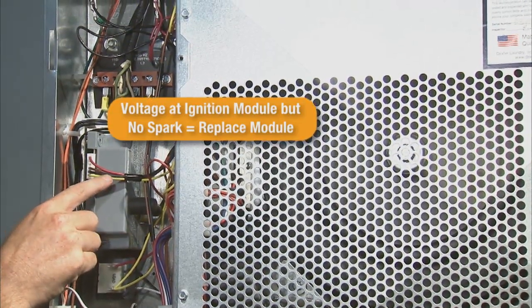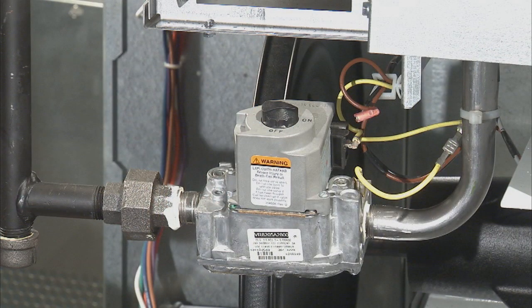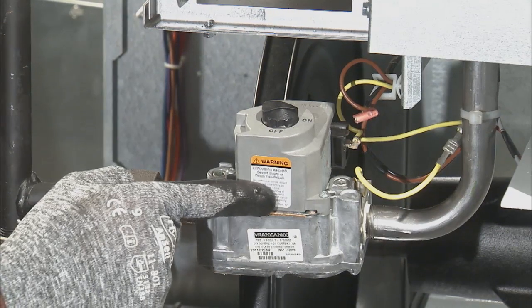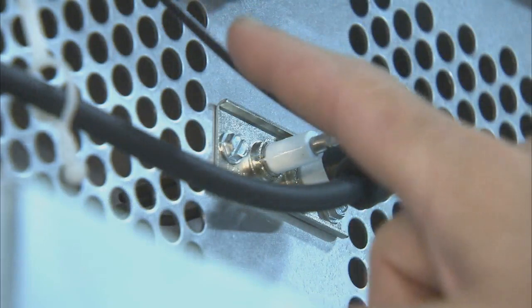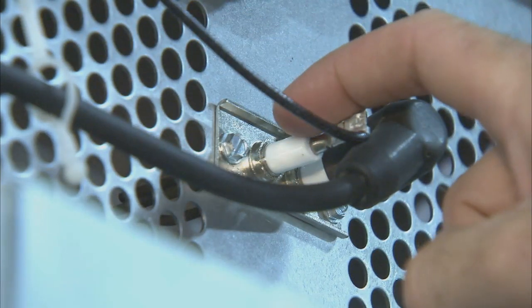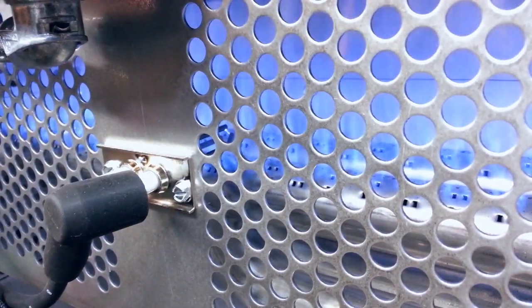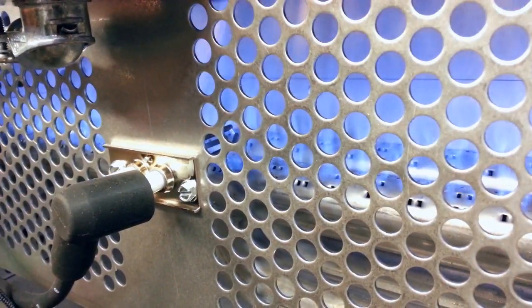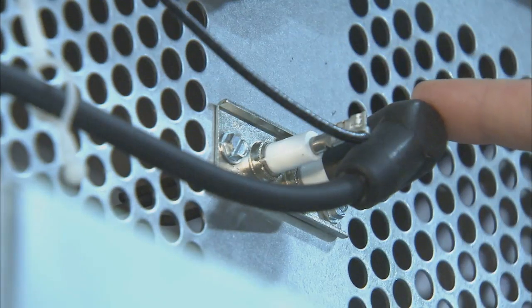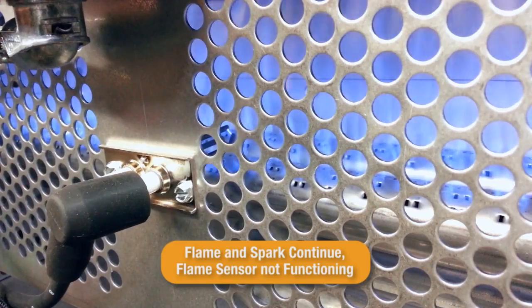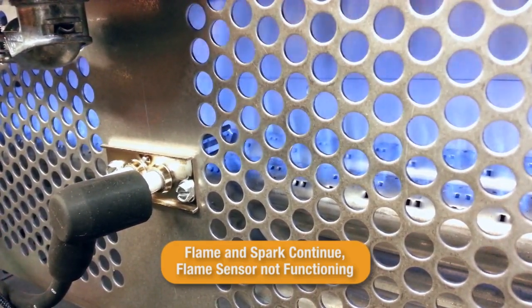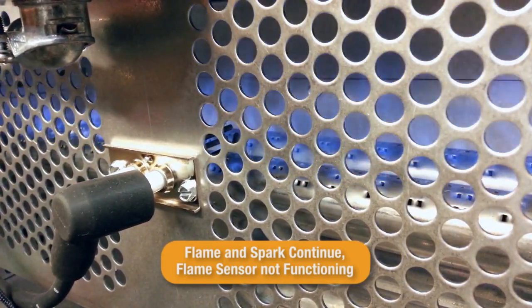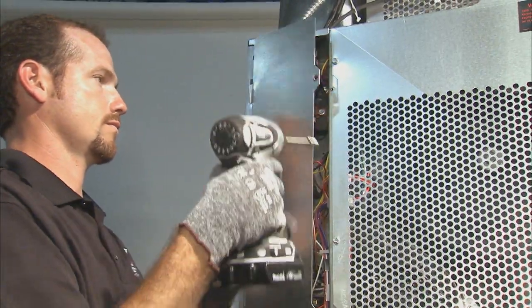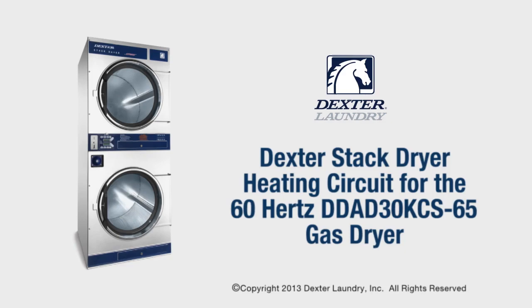If there is sparking but no flame, check the gas supply to the dryer for proper inlet pressure, or it may be necessary to replace the gas valve. As a safety feature, the ignition module also uses a flame sensing circuit. This is designed to stop voltage to the gas valve if there's no flame present at the burner. If the flame ignites, burns for 4 to 10 seconds, and then goes out, or if you see the flame light and the spark is still igniting while the flame is burning, then the flame sensor with the igniter probe needs to be replaced. By following these steps, the cause of the no heat issue will have been discovered and corrected. The dryer is now ready for operation.